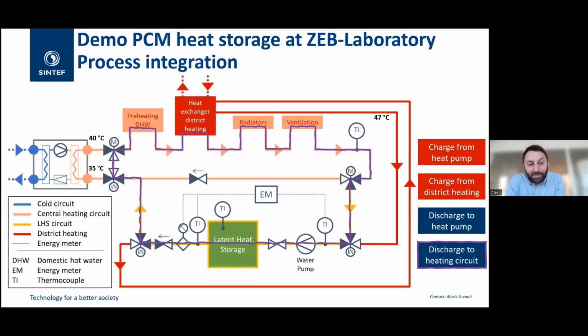But anyways, the thing with the temperature range here is that the niche market for PCM is to go on these places where the temperature range is limited. If you have the freedom to play with 20 Kelvin, 40 Kelvin, then PCM might not be the right solution. But if we have a place with a heat pump where it's restricted, if you want to hold the best energy use, you see here we play between 35 and 40 degrees, and we have the PCM nicely located at 37, 38 degrees for the melting temperature.